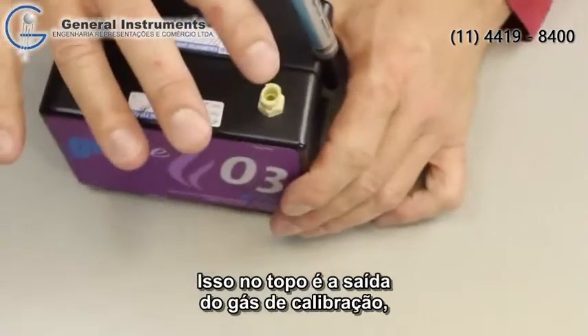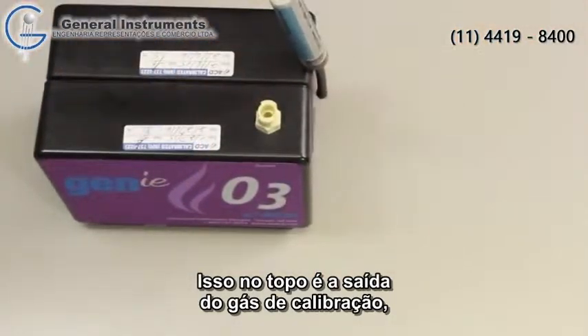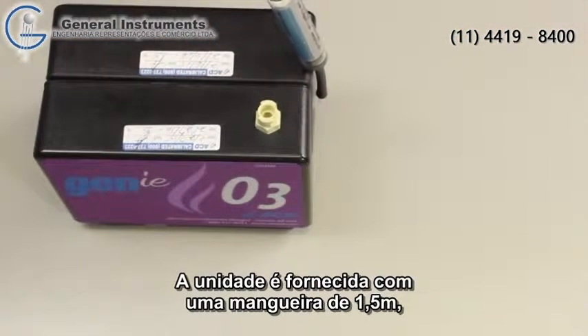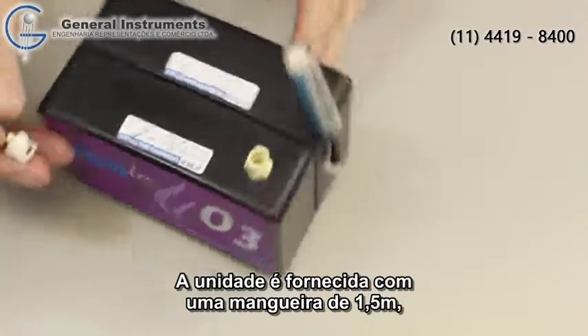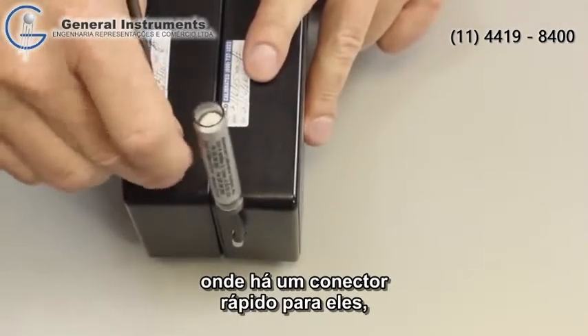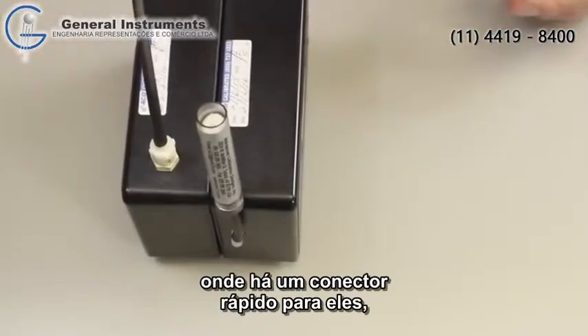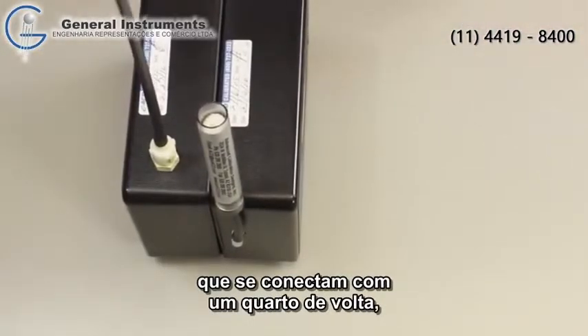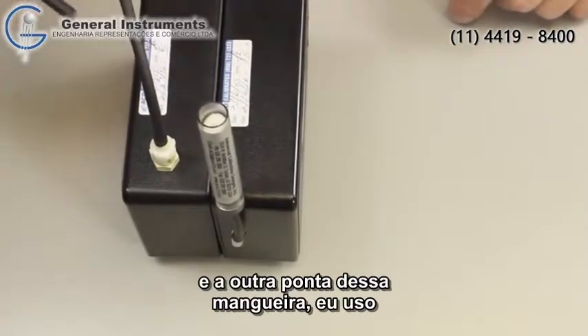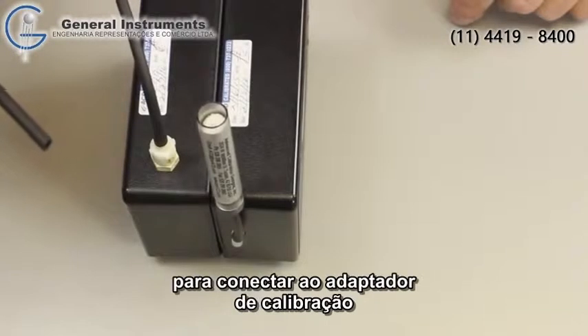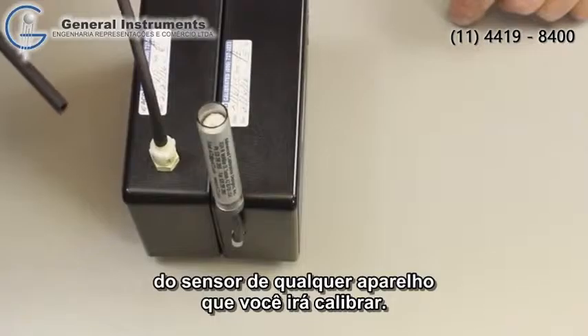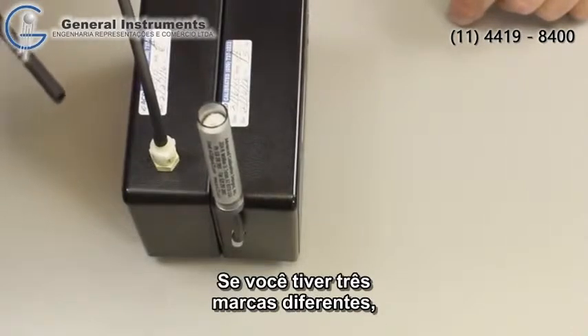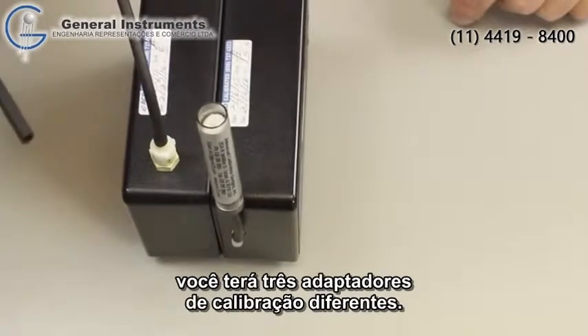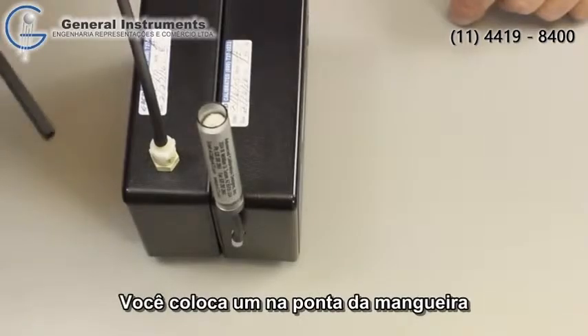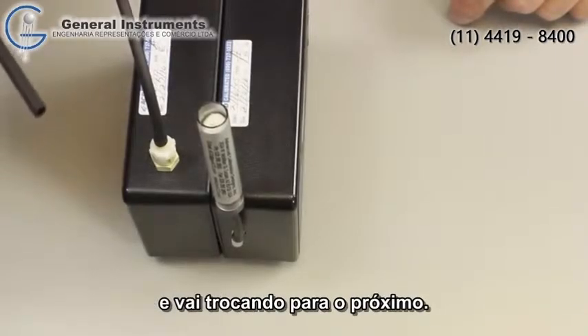This on top is the output of the calibration gas, so that's the outlet fitting. The unit is supplied with a 5-foot hose. There's a quick connect fitting to it, so you give that a quarter turn and you're attached. And then the other end of this hose you use to attach the calibration adapter of whoever's sensor you're going to calibrate. So if you've got 3 different brands, you've got 3 different calibration adapters. You pop one on the end of this hose and then switch it out from one to the next.